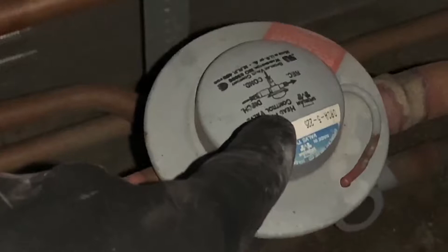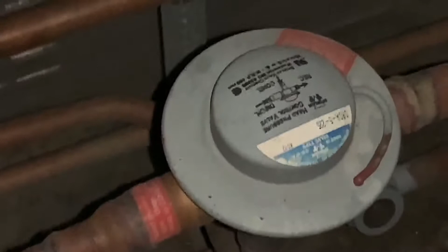Okay, so on the valve, you have three pipes. You have two inlets and one outlet. You have one inlet labeled DSCH, that's discharge, and another one labeled COND, which is condenser. So the DSCH is your discharge line or compressor discharge, and the COND, that's your liquid line from your condenser. And obviously the other one, the one outlet, which says REC, well, that's your receiver. Okay, now let's trace the piping out and see how it's piped.